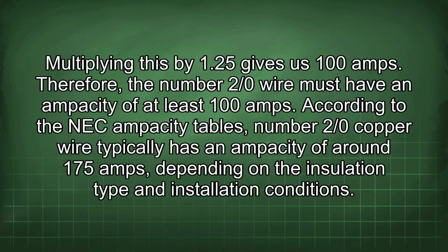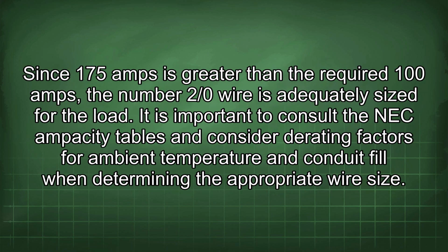According to the NEC ampacity tables, number 2/0 copper wire typically has an ampacity of around 175 amps, depending on the insulation type and installation conditions. Since 175 amps is greater than the required 100 amps, the number 2/0 wire is adequately sized for the load.